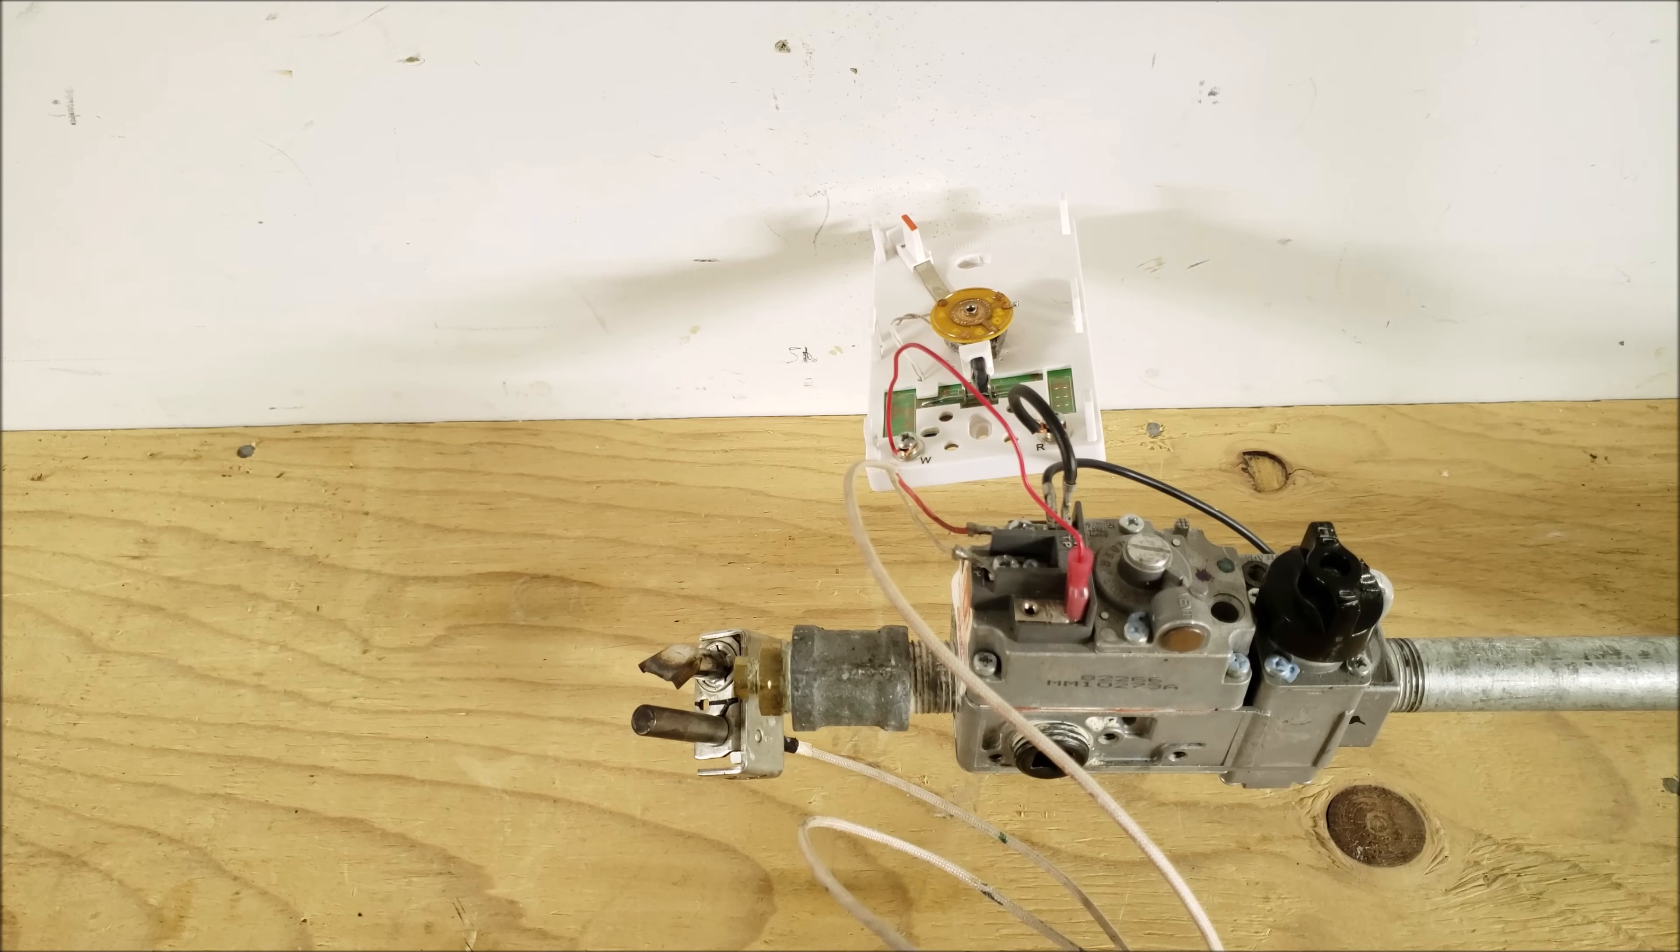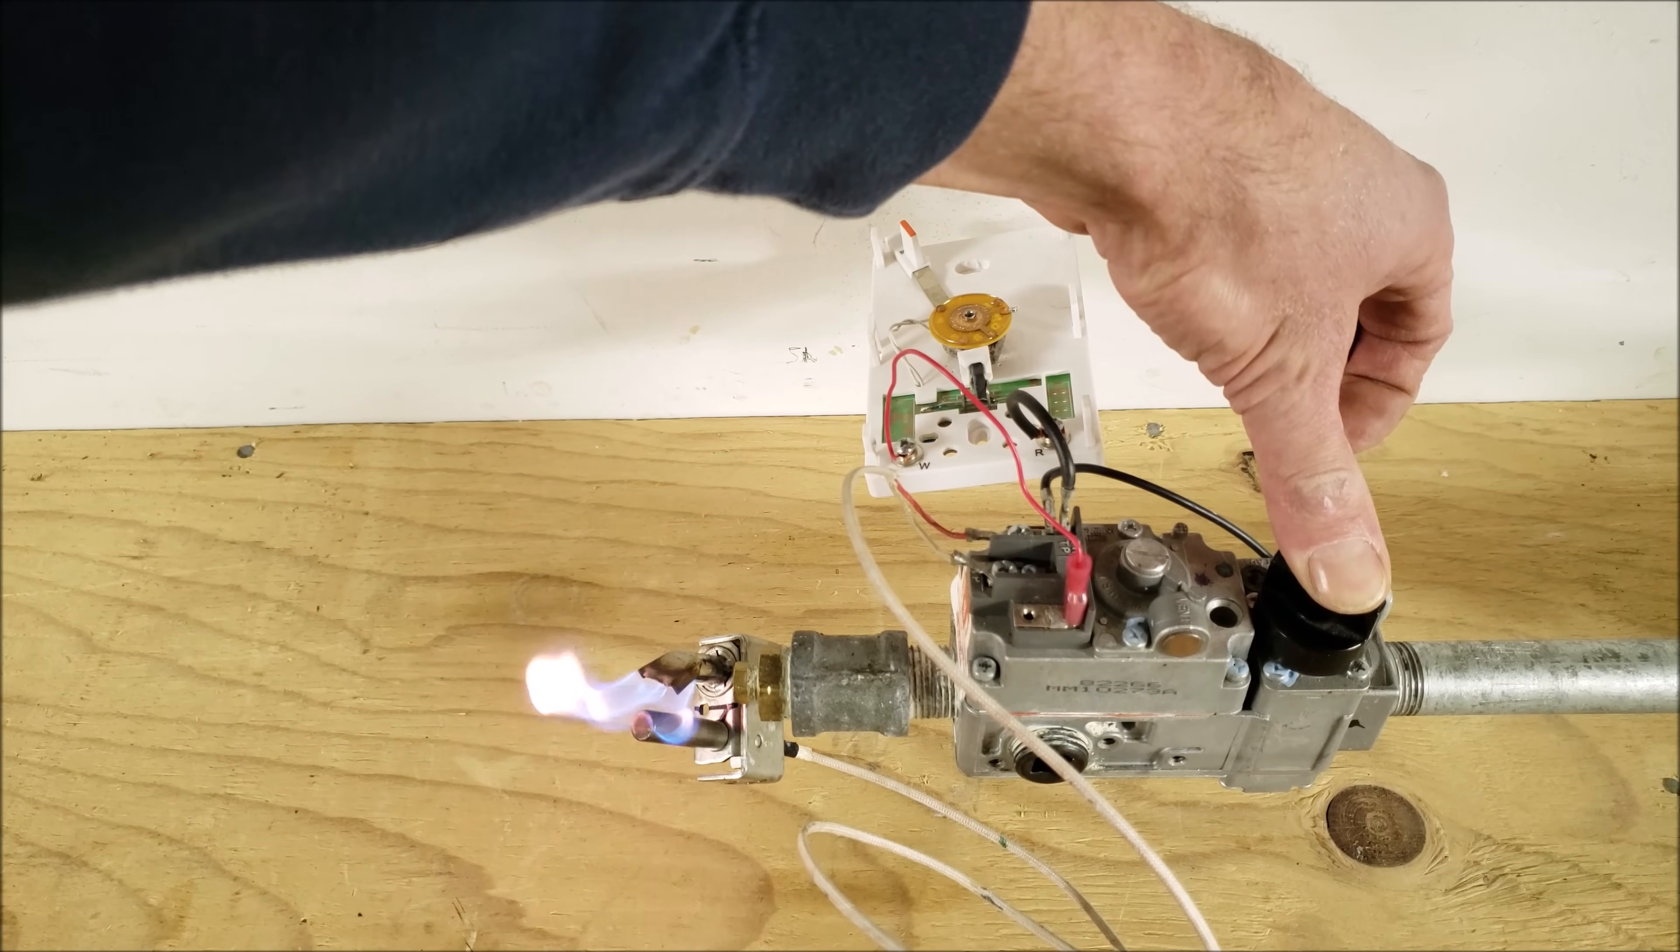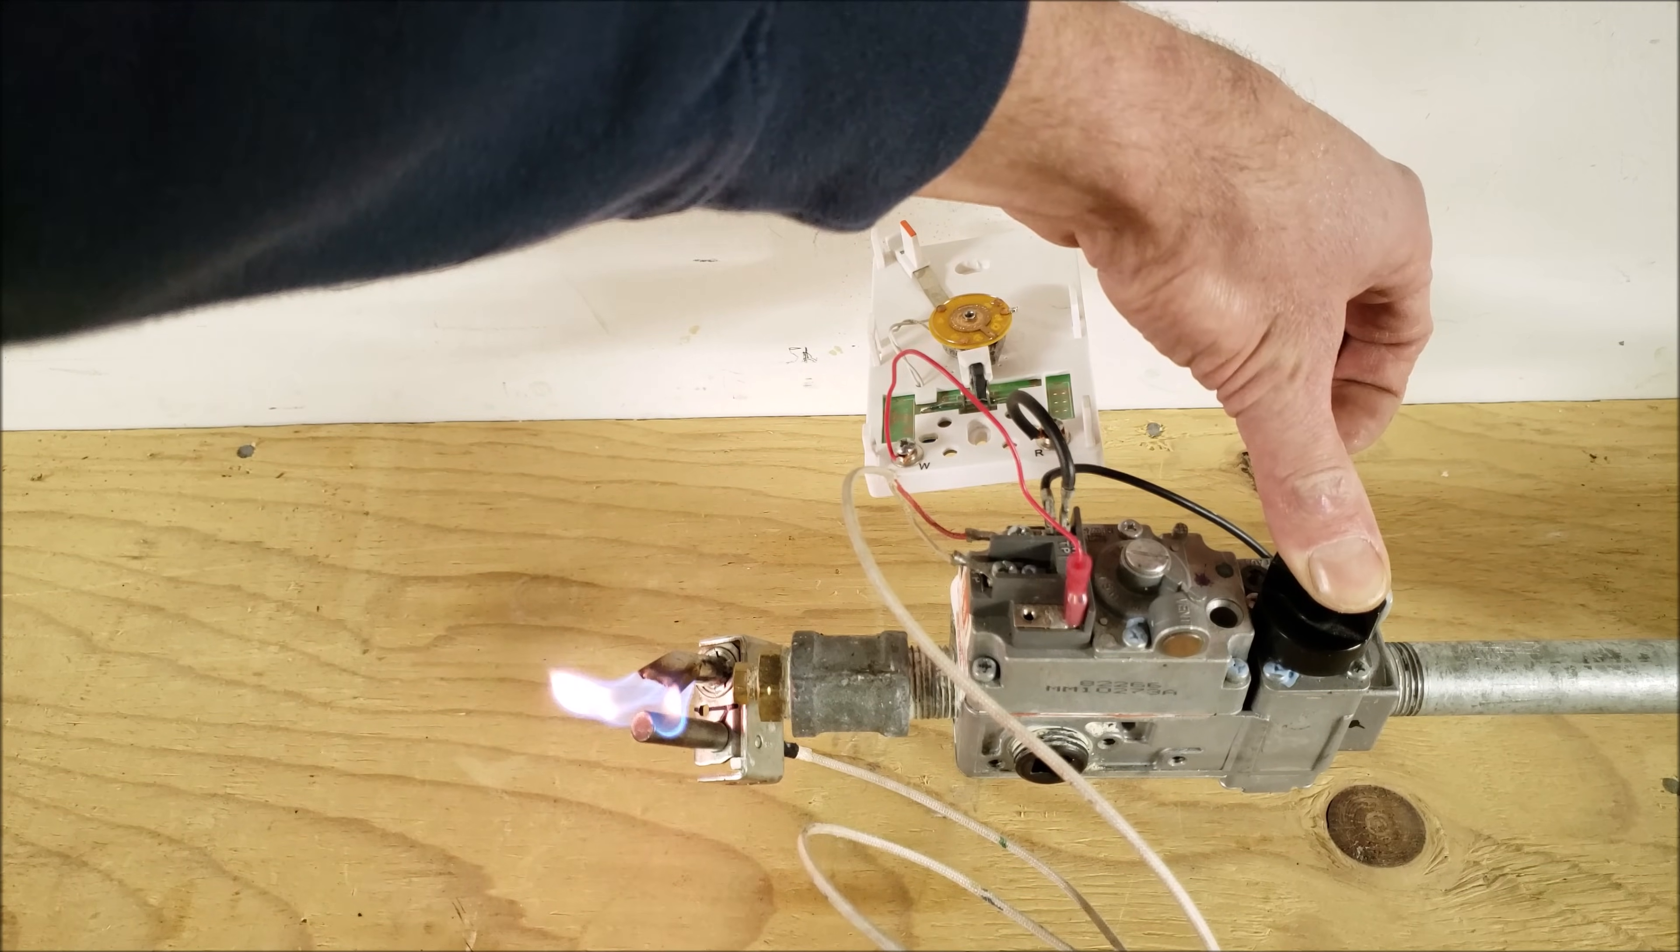So in order to turn your pilot on we're going to turn this button over to the pilot and have that lined up right there and then we're going to press down on that. Typically you're going to hold that button down for about 45 seconds but it may not take that long in order for the thermopile to heat up and generate enough millivolts to keep the solenoid held in place.